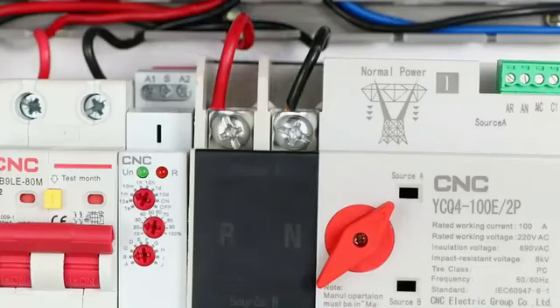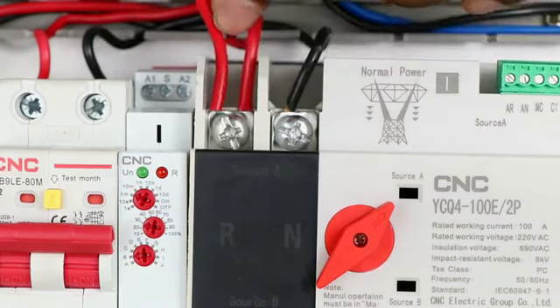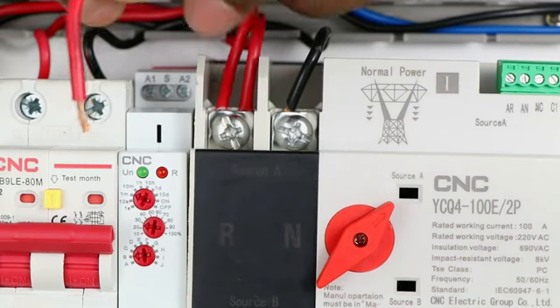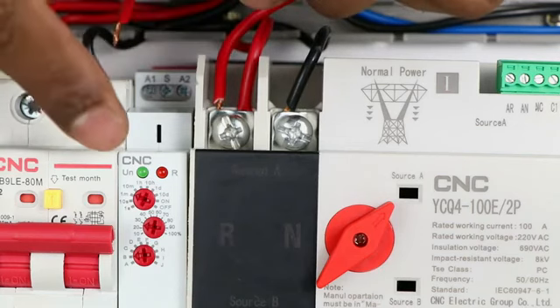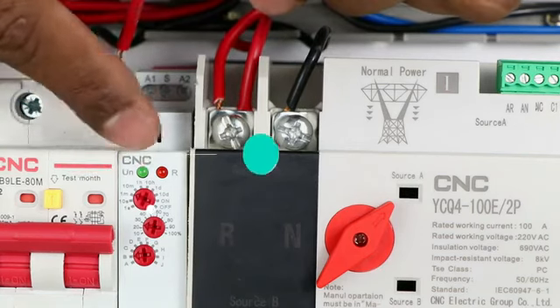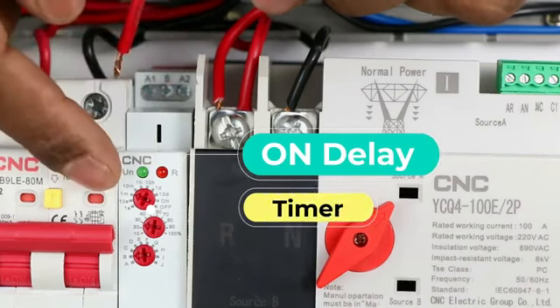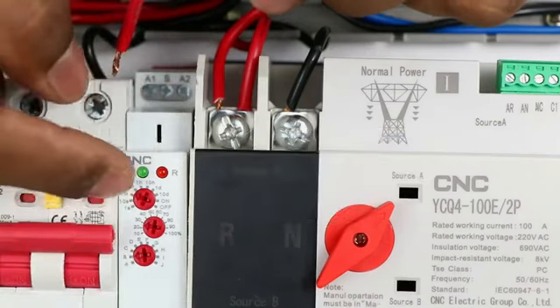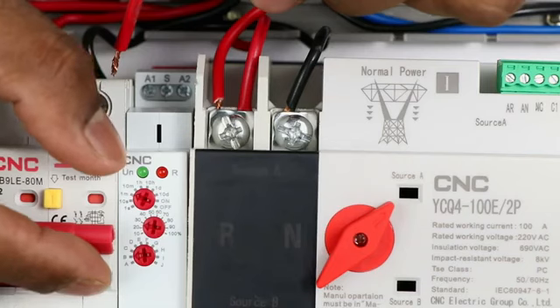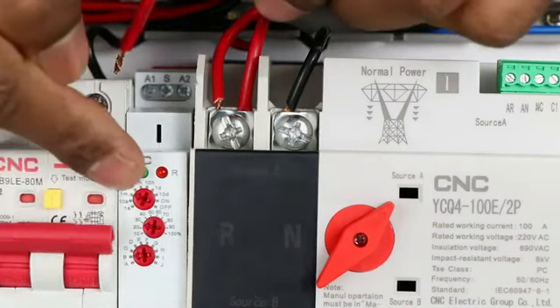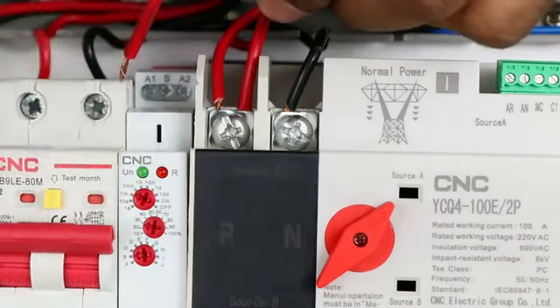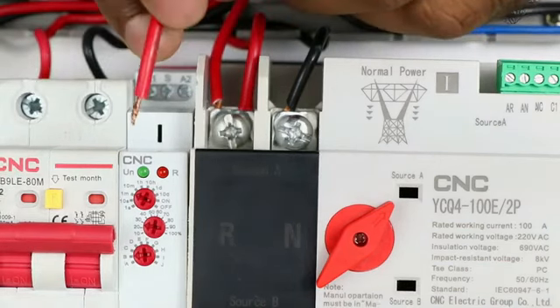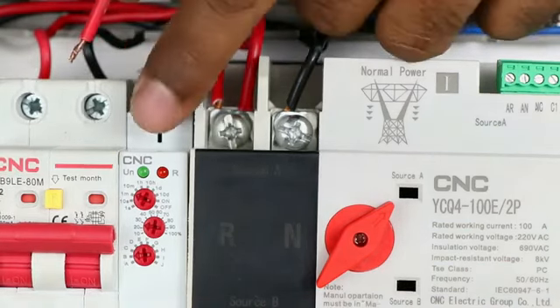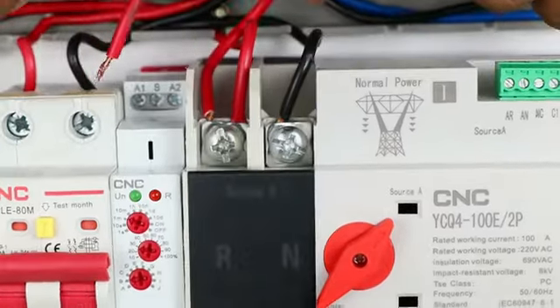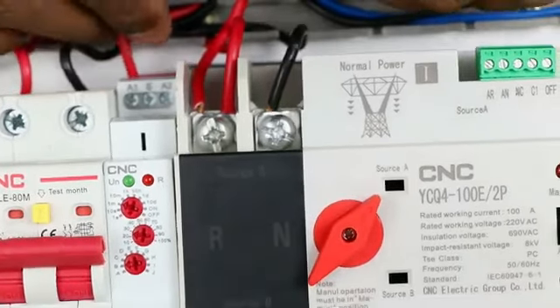What we have to do is, at our main power supply terminal, connect one more wire at the same point. The other end of the wire is to be connected at the on delay timer. Remember, the timer which you are using must be an on delay timer. The timer I am using here is a multifunction timer which can be used as an on delay timer. That is why I am referring to this as an on delay timer. Okay. So the other end of the wire is to be connected at the A1 terminal of the timer. I connected the wire with this terminal.